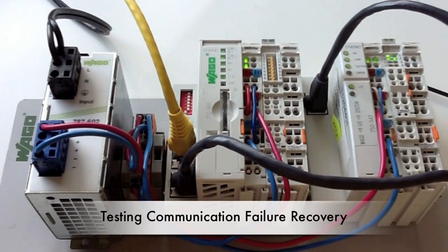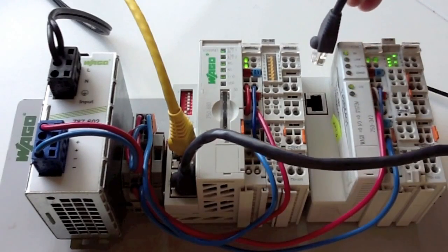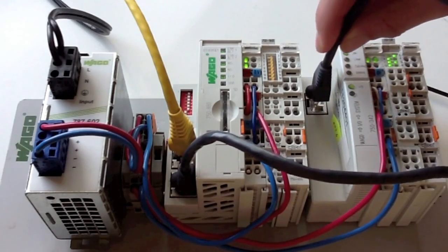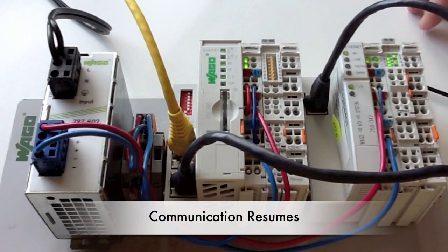And now we can test the communication failure. I'm just going to unplug the Ethernet cable. You can see it holds the last state. When I plug it back in, a second or two later, the communication resumes. And that concludes our video.